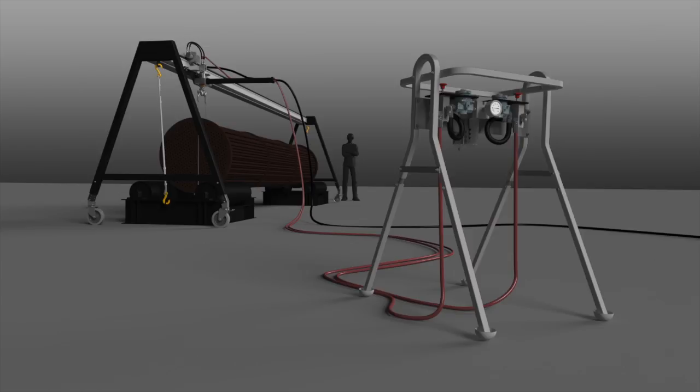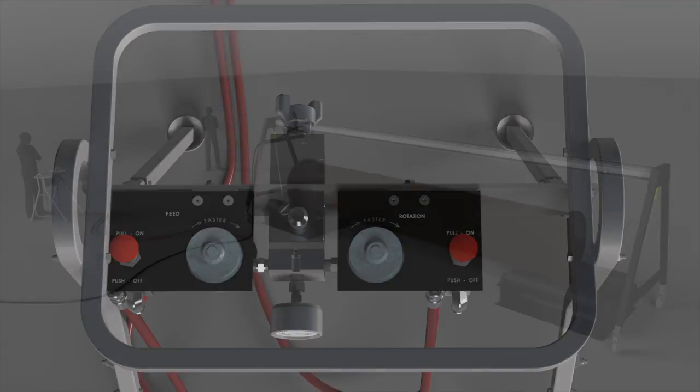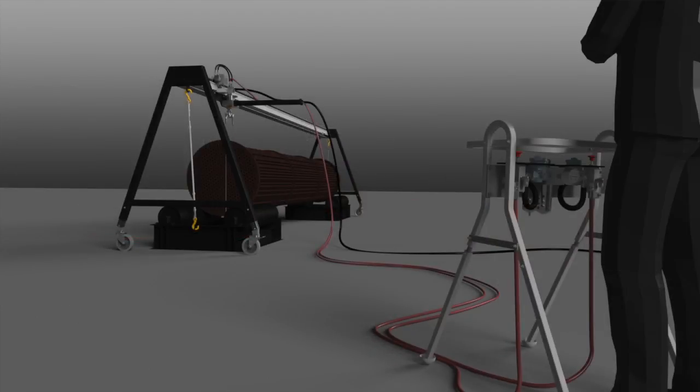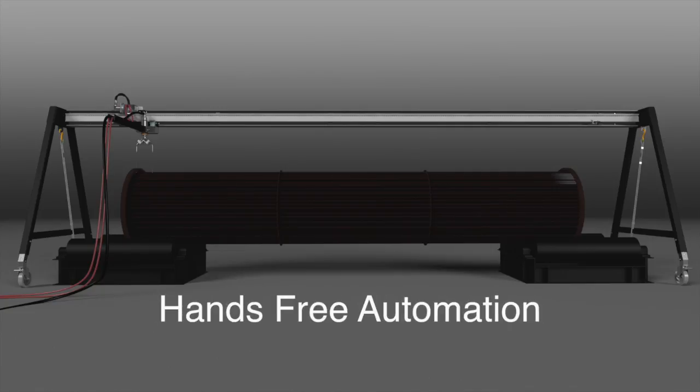Operation of the BundleBlaster is controlled remotely using a control box. This allows the operator to remain safely outside the blast zone and still have precise control over the traverse speed of the tractor and rotation speed of the head. This automated control is what enables you to optimize blast settings for the specific surface being cleaned. The BundleBlaster also eliminates the need for using handheld shotgunning tools so that contractors can meet hands-free safety requirements.